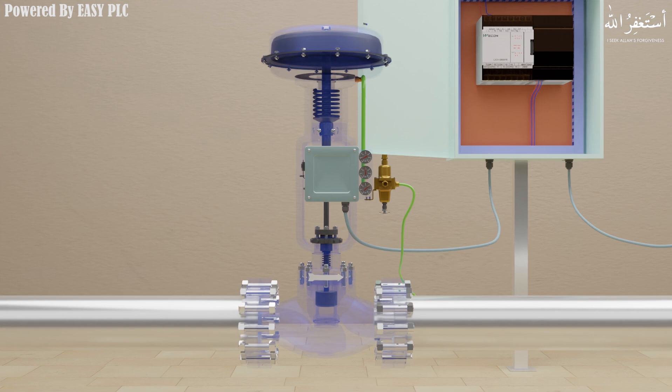Because of how pneumatic actuators are built, a control valve will move to a specific position when a loss of the control signal occurs. As the supply air pressure is increased, the rubber diaphragm pushes against the spring and moves the valve stem upward out of the valve body. As the supply air pressure is reduced, the spring will move the valve stem inside the valve body.